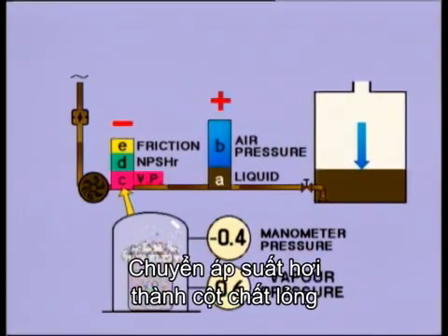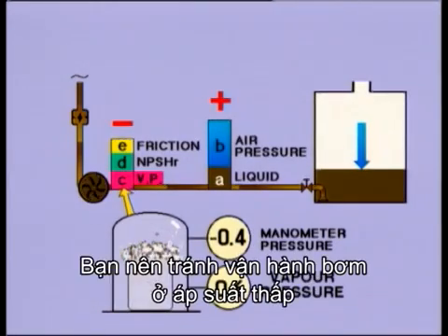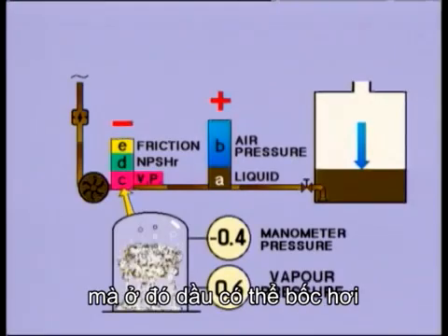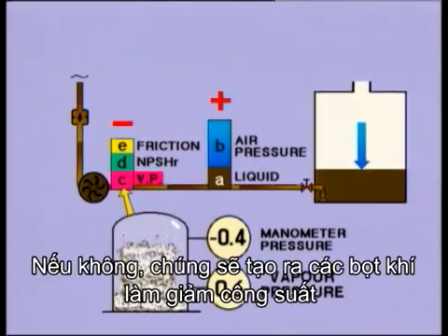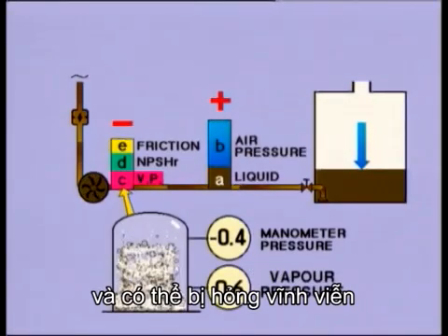Convert the vapour pressure into a liquid column. You should avoid operating pumps at such a low pressure where oil gases off. If you don't, they will cavitate, lose capacity and be permanently damaged.